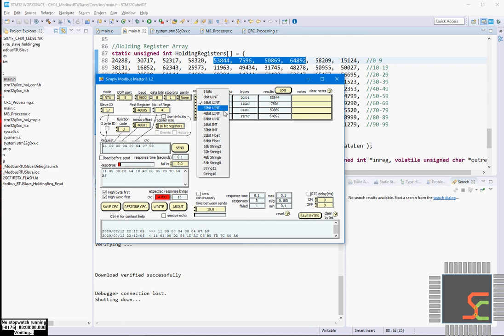Now as I also said, the master will represent that data. Like suppose if I say 16-bit int, it did not affect this one. Let's try this one. Yeah. So when the master is configured with a different data type, the result gets changed very drastically. So it is the master's responsibility to keep in mind what data type I am requesting.